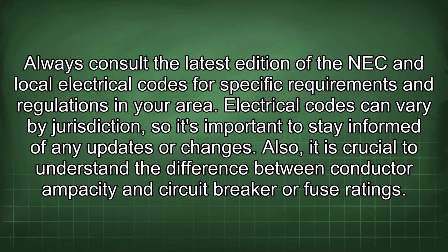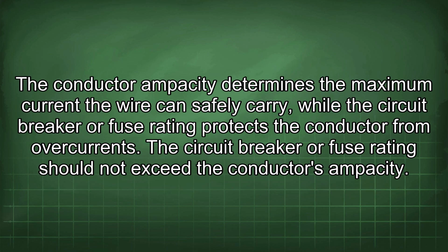Always consult the latest edition of the NEC and local electrical codes for specific requirements and regulations in your area. Electrical codes can vary by jurisdiction, so it's important to stay informed of any updates or changes. Also, it is crucial to understand the difference between conductor ampacity and circuit breaker or fuse ratings. The conductor ampacity determines the maximum current the wire can safely carry, while the circuit breaker or fuse rating protects the conductor from overcurrents. The circuit breaker or fuse rating should not exceed the conductor's ampacity.